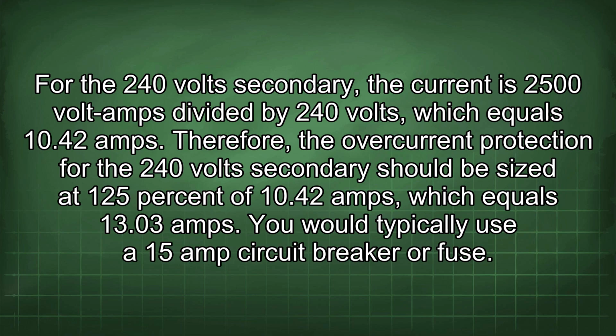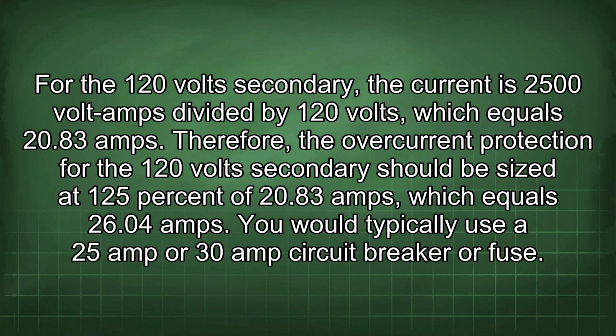For the 240 volt secondary, the current is 2500 voltamps divided by 240 volts, which equals 10.42 amps. Therefore, the overcurrent protection for the 240 volt secondary should be sized at 125% of 10.42 amps, which equals 13.03 amps. You would typically use a 15 amp circuit breaker or fuse. For the 120 volt secondary, the current is 2500 voltamps divided by 120 volts, which equals 20.83 amps. Therefore, the overcurrent protection for the 120 volt secondary should be sized at 125% of 20.83 amps, which equals 26.04 amps. You would typically use a 25 amp or 30 amp circuit breaker or fuse.